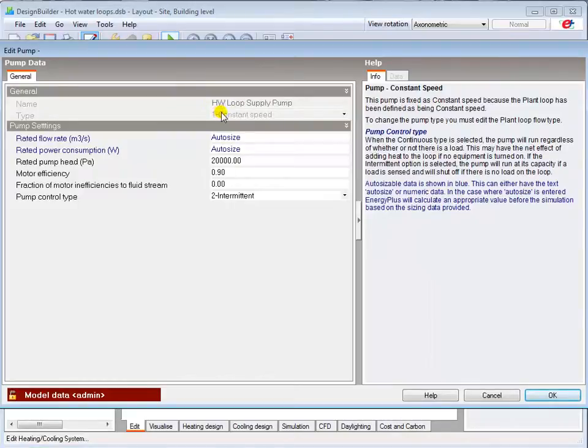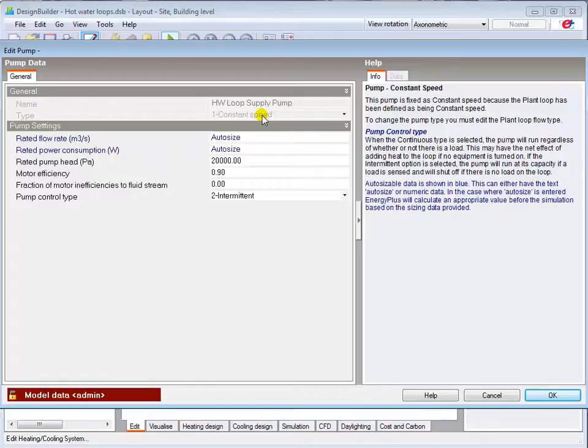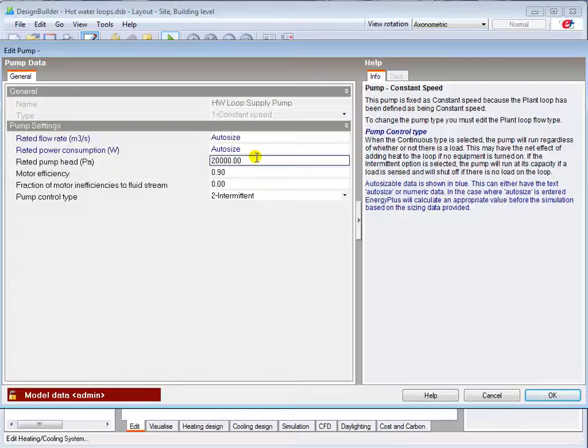The pump type is fixed at either constant or variable speed depending on the setting made at loop level. It's not currently possible to calculate system resistance in the simulation, so you'll need to input a suitable pump head using design data if you wish to simulate pump energy consumption more accurately.